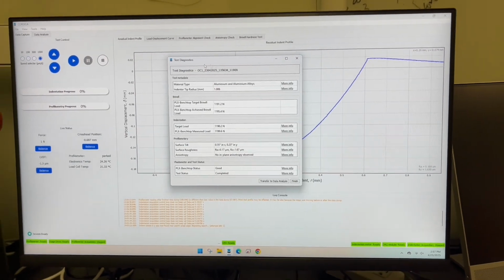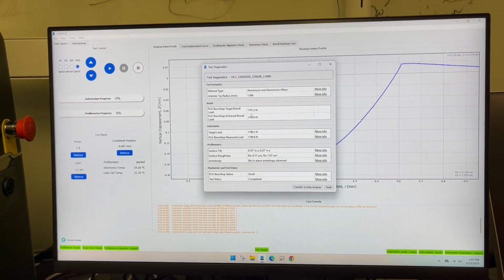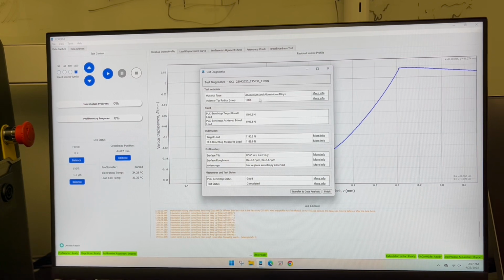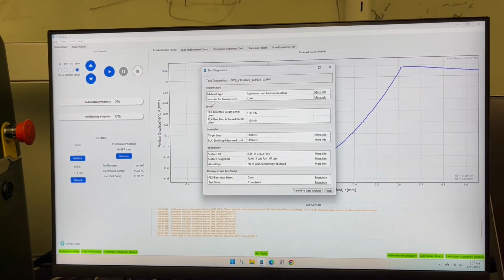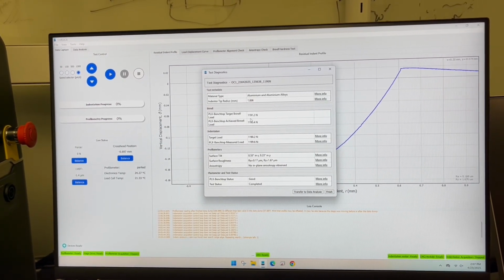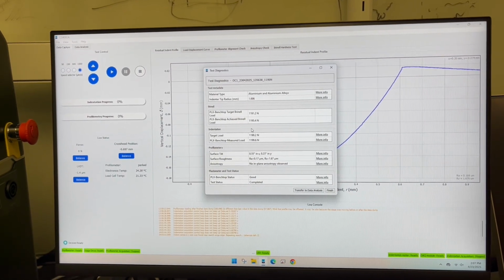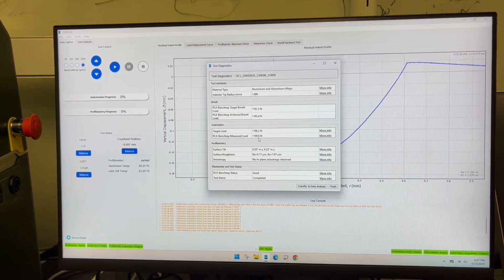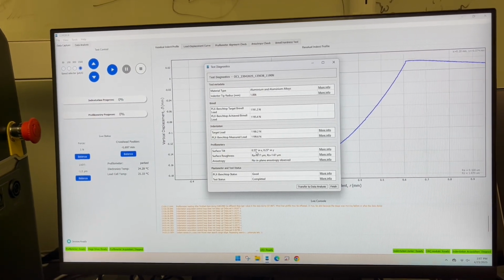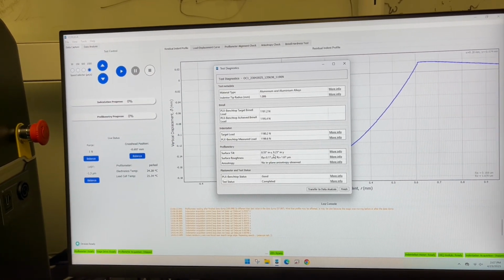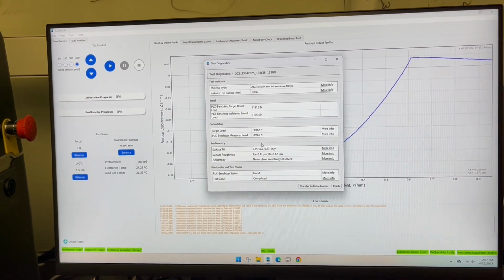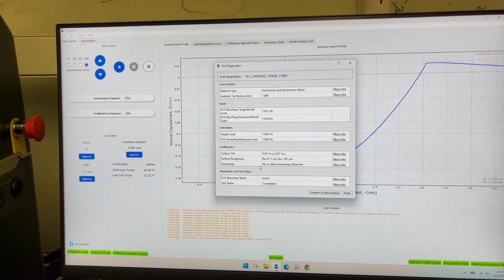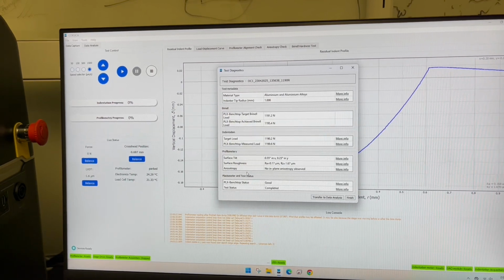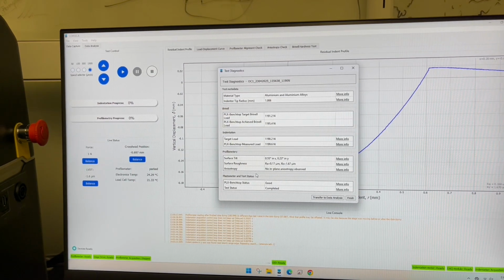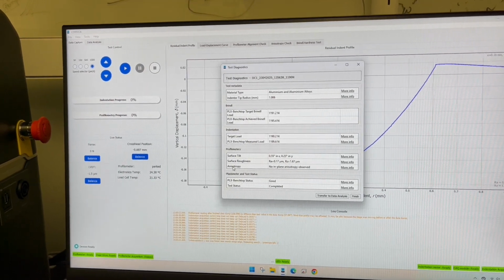Once you've completed the test, a test diagnostic window will pop up, displaying the different parameters done in the test. For example, the indenter tip radius, the parameters of the Brinell hardness test, the target and achieved load of the indentation test itself, other parameters for the profilometry detailing the surface tilt, surface roughness, and isotropy, which shows if the hardness of the material in one direction is more or less than the other direction. The test statuses will be yellow or red if something went wrong, but in this case, everything was okay.